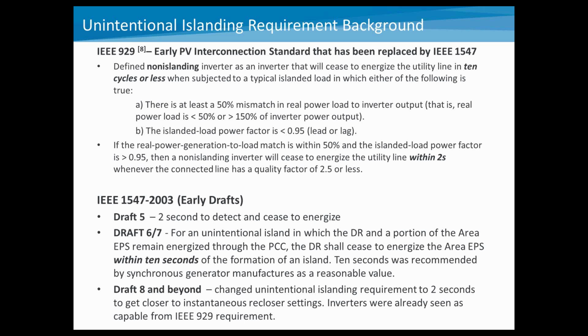If we look at 1547 and go through some of the various drafts, typically the drafts before draft 5 had this 2 second requirement in there. There were actually some points in time during drafts 6 and 7 when we bumped that up to 10 seconds. That was recommended a lot by synchronous generator manufacturers that weren't using active anti-islanding techniques, because they recommended that value. And then in drafts 8 and beyond, the requirement came back to 2 seconds.